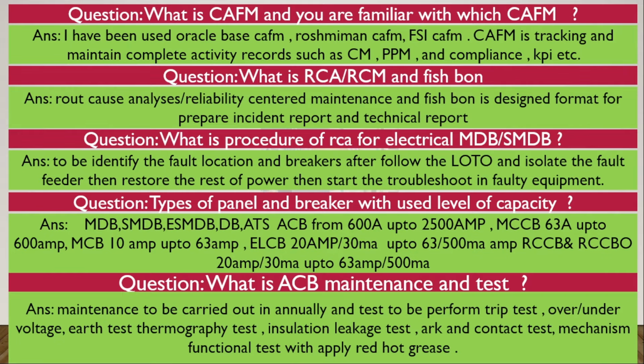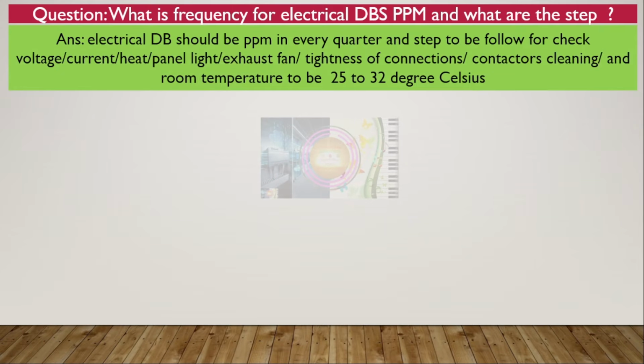So maintenance is to be carried out annually, and tests to be performed: trip test, over and under voltage test, earth test, thermography test, insulation leakage test, arc and contact test, mechanism functional test with red hot grease applied also. So for ACB we have to use the red hot grease.